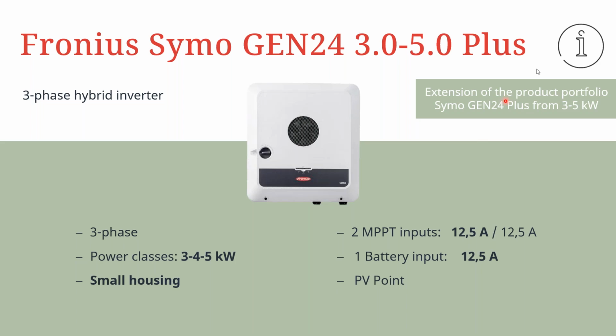We also have another variant within the Symo GEN24 Plus. This is the smaller power class of the Simo series, which is 3 to 5 kilowatts. It is available in 3, 4, and 5 kilowatts. It also comes in a comparatively smaller housing. With regards to the MPPTs, here we have the current handling capacity of 12.5 amps for each MPPT, and the battery input can also take a maximum of 12 amps for discharging as well as charging. Because of this, the smaller variant of the Symo GEN24 Plus is not able to give you full backup, but you still are able to get the PV point, which is the opportunity power that can be obtained from the GEN24 without a battery storage.